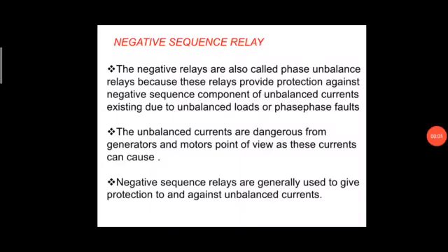Now, next one is the negative sequence relay. Negative sequence relays are also called phase unbalance relays because these relays provide protection against the negative sequence component of unbalanced currents existing due to unbalanced loads or phase-to-phase faults.